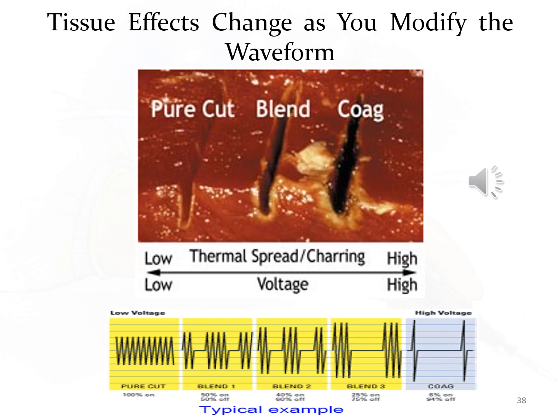Electrosurgical generators are able to produce a variety of electrical waveforms. As waveforms change, so will the corresponding tissue effect. Using a constant waveform like cut, the surgeon is able to vaporize or cut tissue. This waveform produces heat very rapidly.